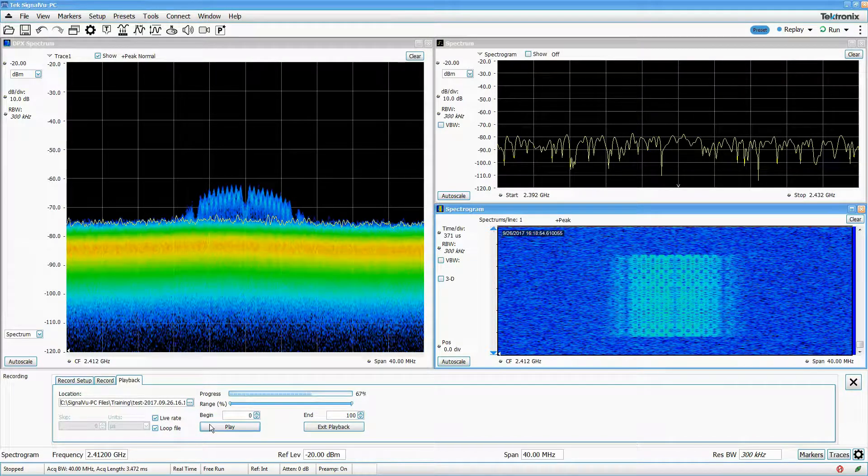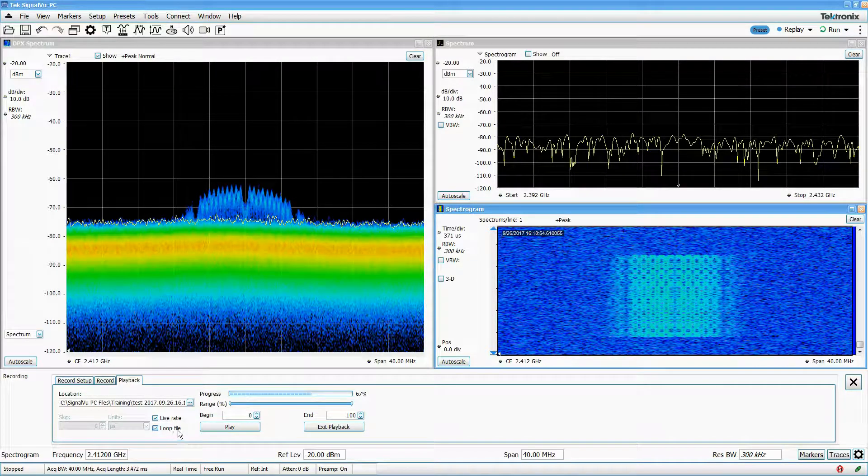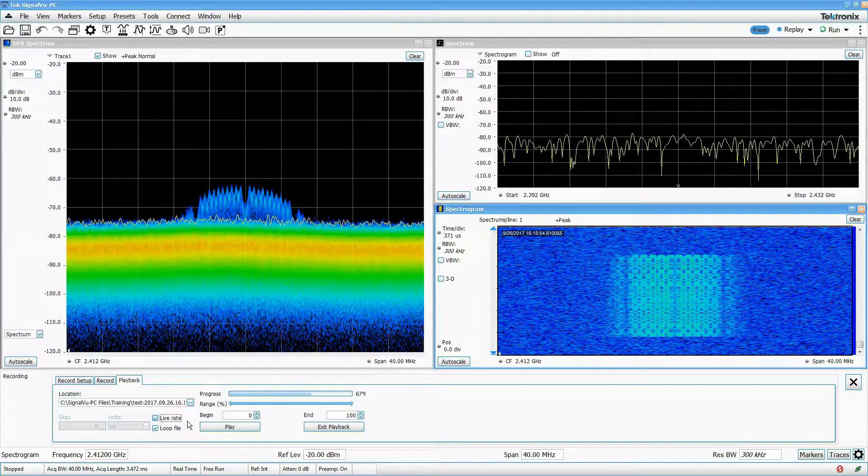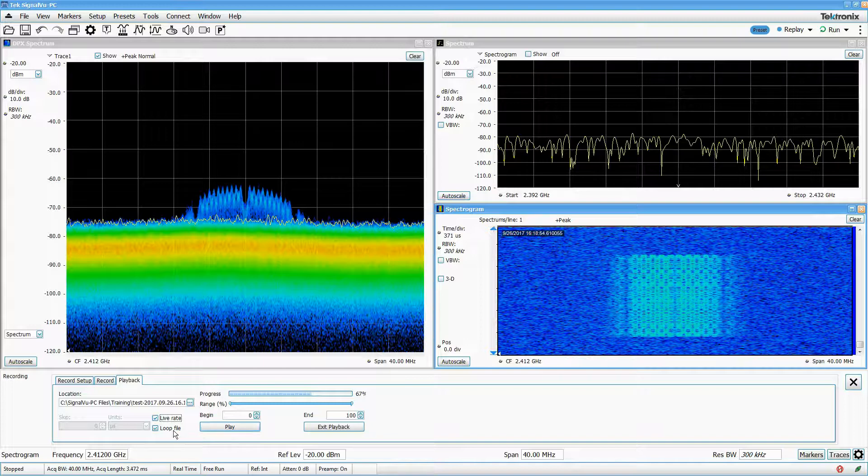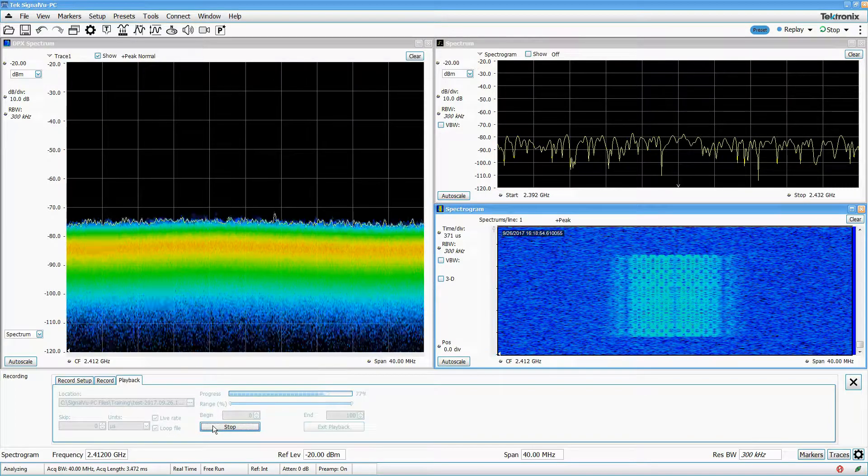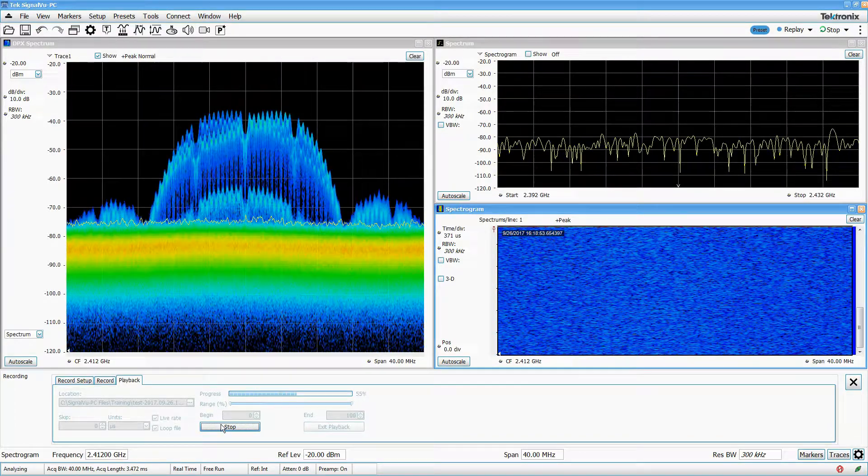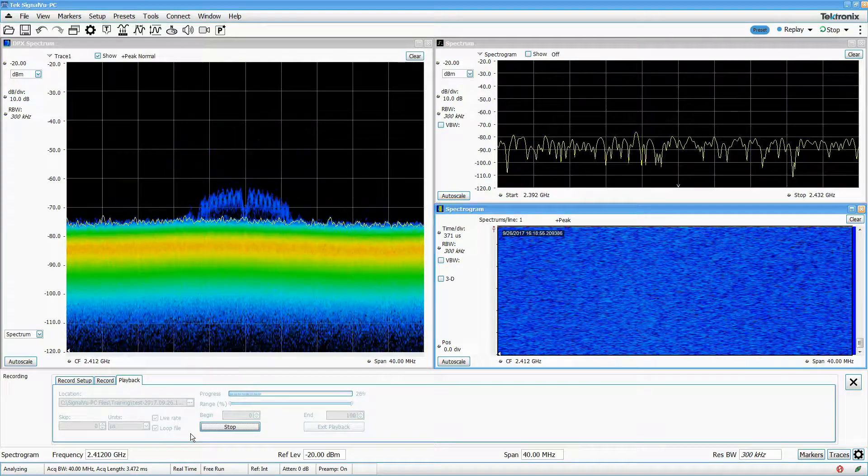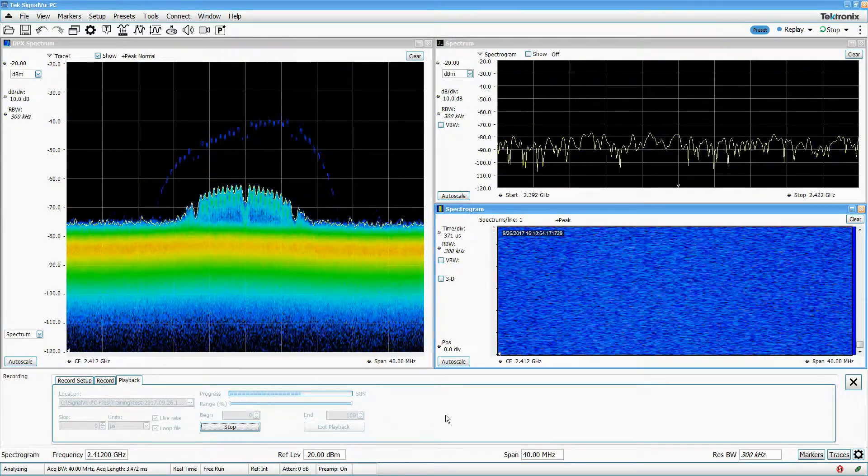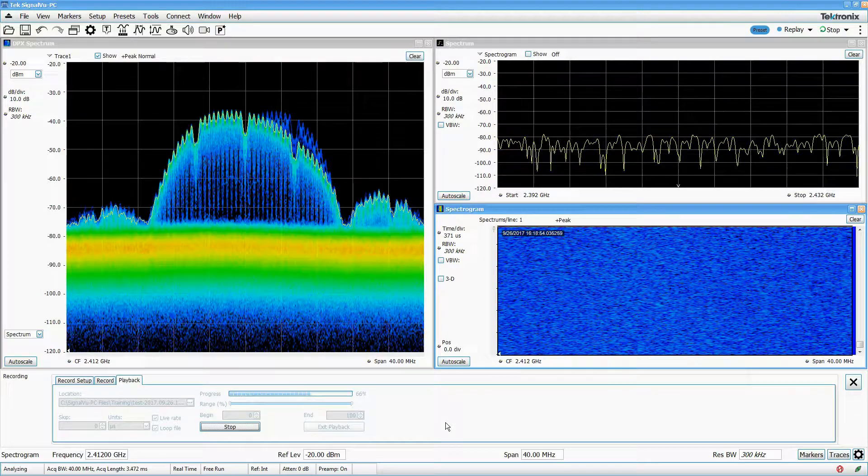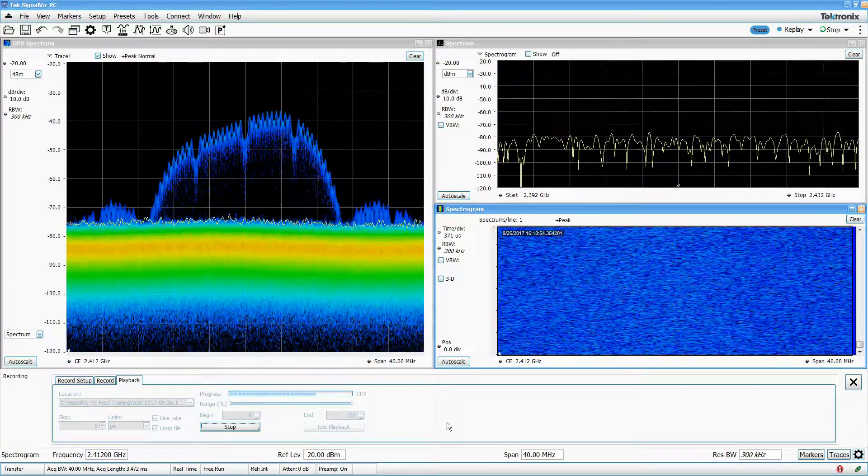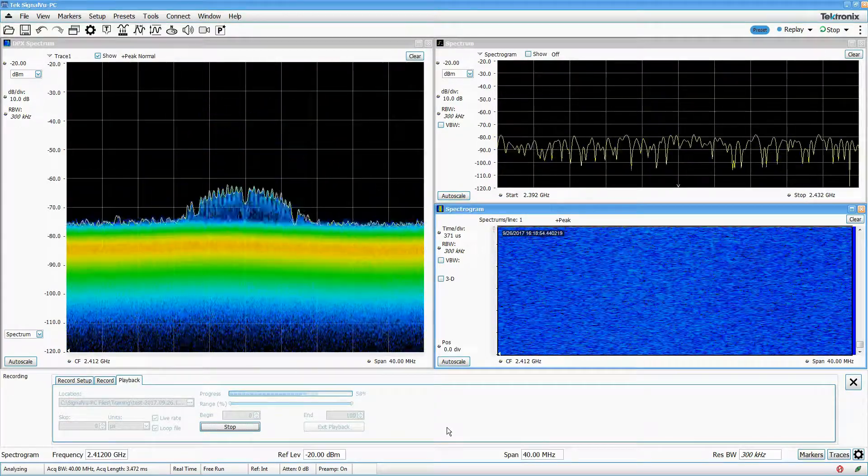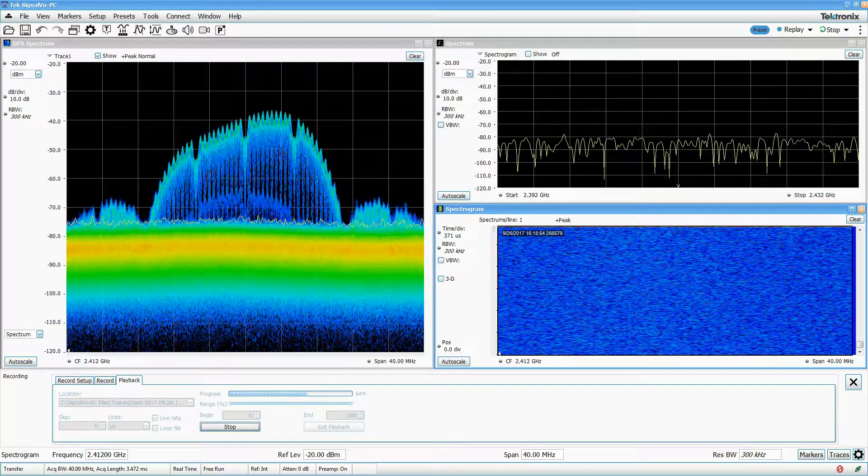You can play the file back at a live rate, meaning SignalVu-PC will treat the data in the file as if it was coming from a real instrument, processing as much as it can and skipping some data. Alternatively, you can play the data back at a non-live rate, meaning that SignalVu-PC will pause the flow of data from the file while it processes data, resulting in the analysis of every single sample in the file. It takes much longer to play back a given data file this way, but it ensures that you don't miss a single sample.